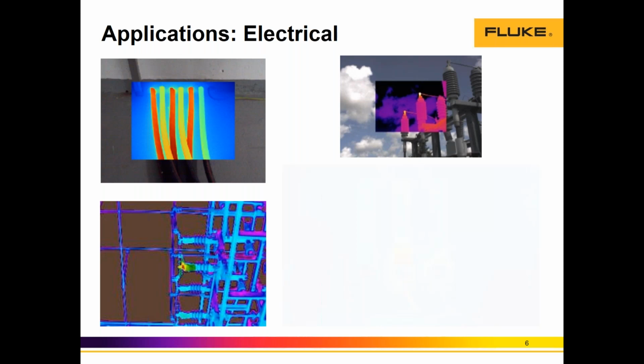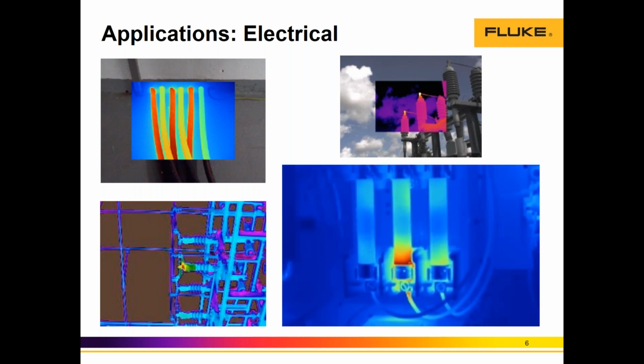You can see here a couple of examples in substation applications. There's a high resistance connection, possibly due to corrosion. Here's another one: a connector above the bushing cap to the bushing rod that's normally hotter. On the bottom right area, there's a center fuse which is definitely having a problem, an isolated issue, which tells us that thermally there's a problem, an indicator that something's not right.